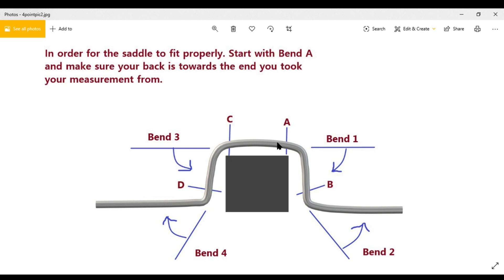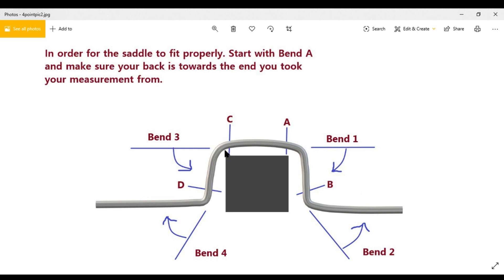When you start bending Points A and B, make sure your back is facing the side that you measured from. So if you measured from one end to get your A measurement, keep your back to Points A and B while bending. When you bend the second offset — C and D — A and B should now be in front of you.